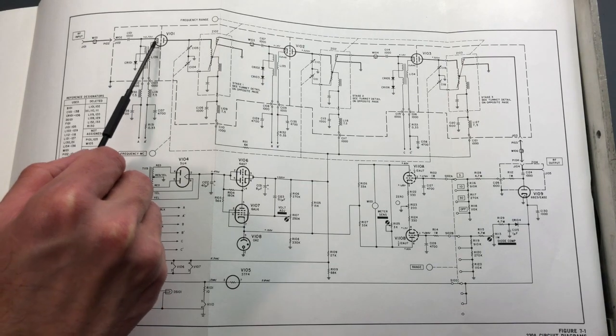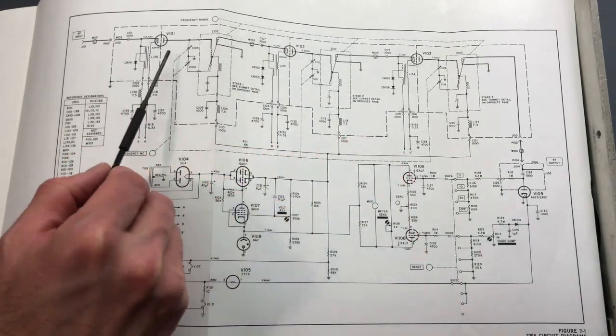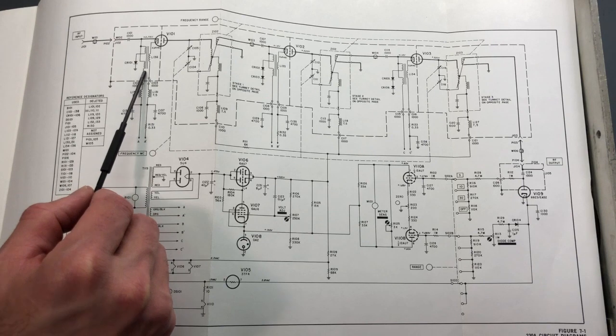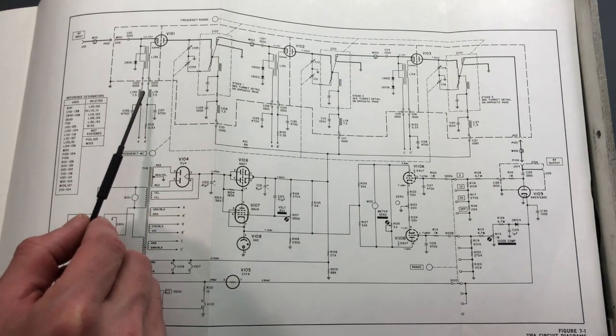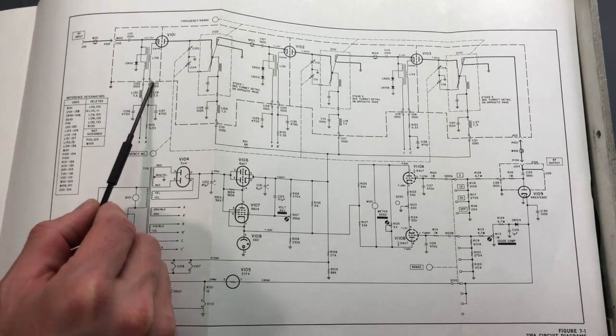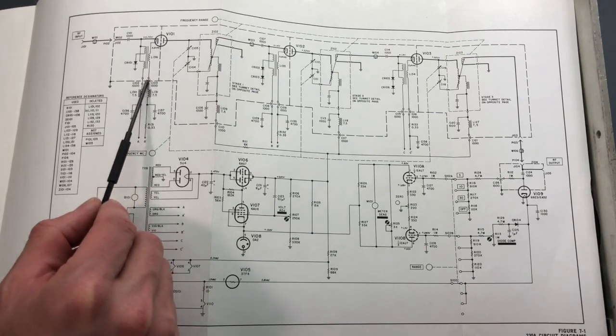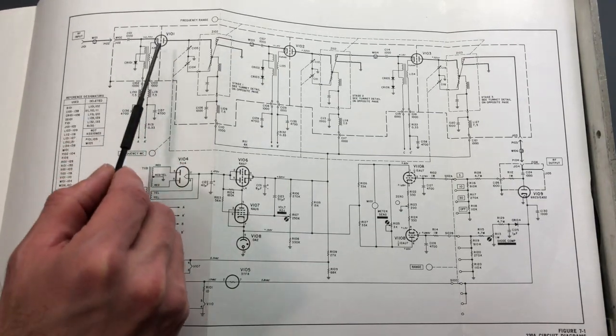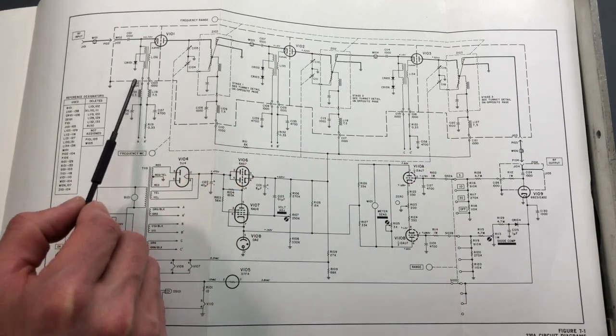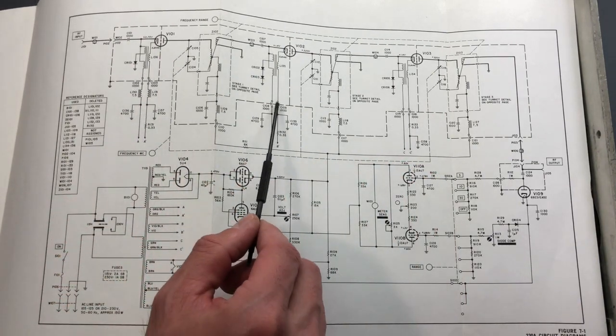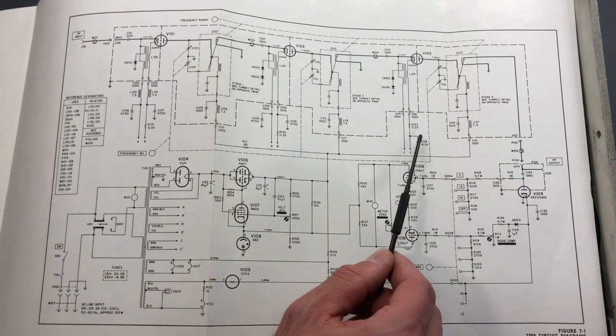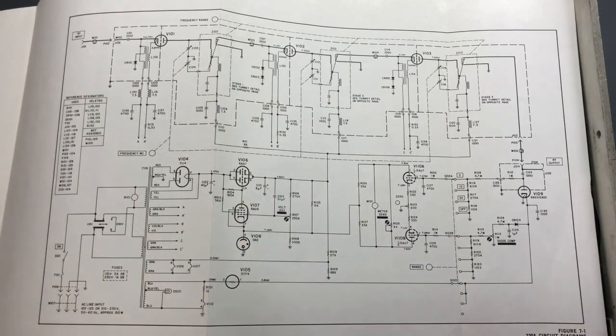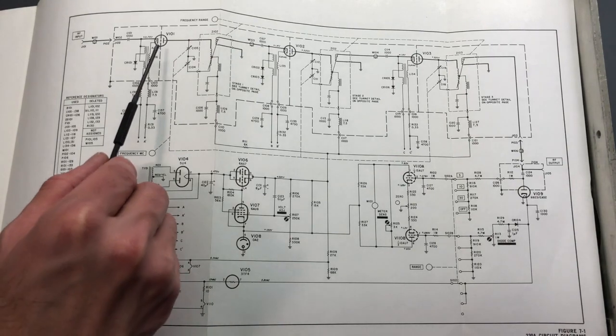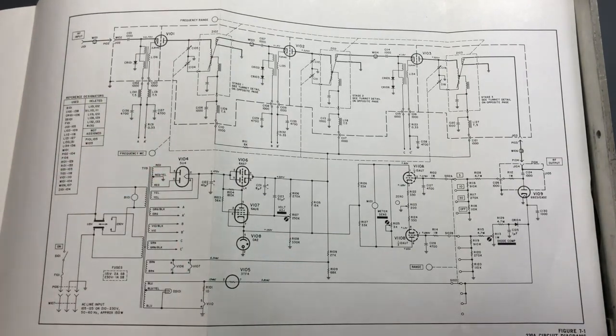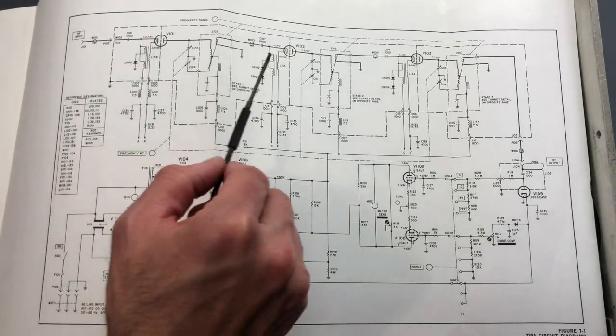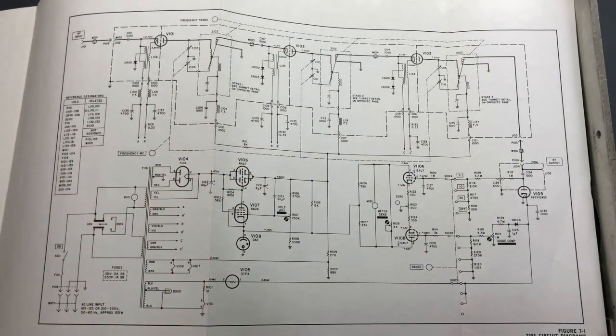Now you can see the filament is shown on these three tubes, and that filament has some additional filtering right here through some inductors, some capacitors, these feed-through capacitors right here. This dashed line is indicating that enclosed box that holds the amplifier section. These capacitors are feed-through caps for the filament lines you can see there and over here. Some additional filtering, resistor, and so on, just to ensure that this is a very clean AC input on those tubes. You can see it's marked as 5.8 volts AC on those three tubes.